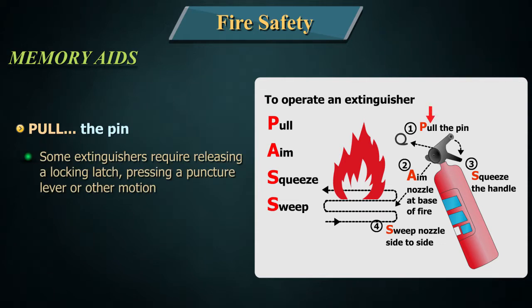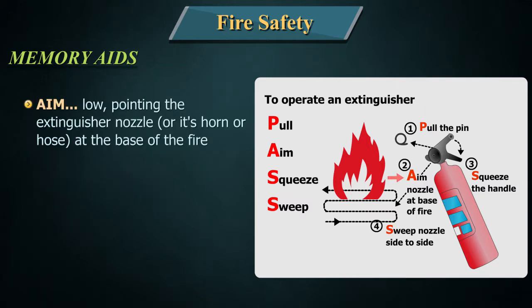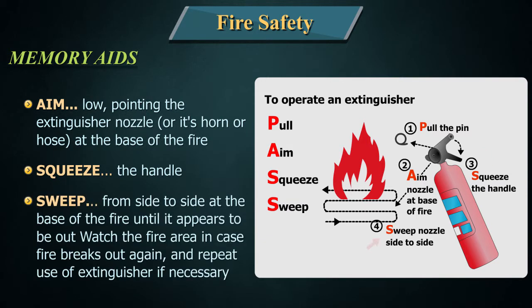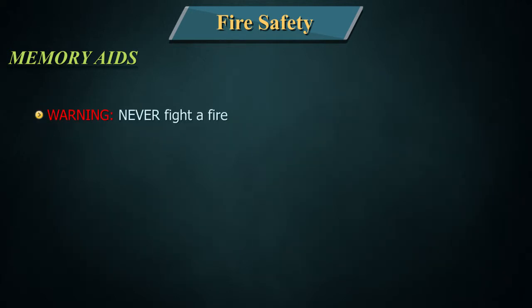Aim low, pointing the extinguisher nozzle, horn, or hose at the base of the fire. Squeeze the handle — this releases the extinguishing agent. Sweep from side to side at the base of the fire until it appears to be out. Watch the fire area in case fire breaks out again and repeat the use of the extinguisher if necessary.